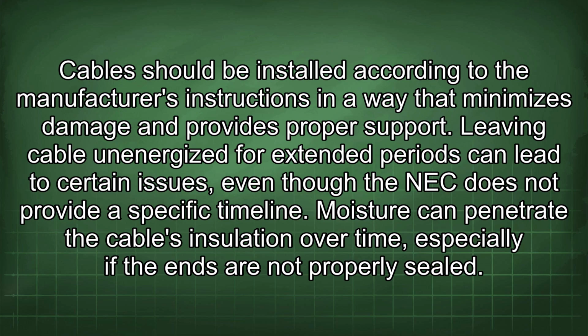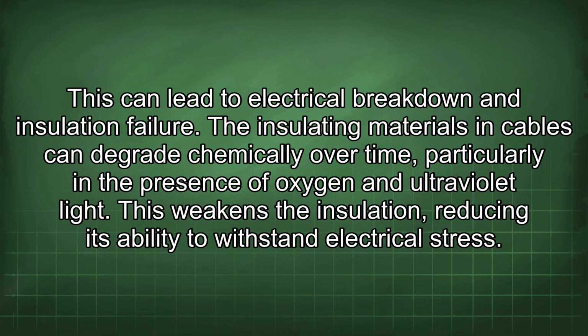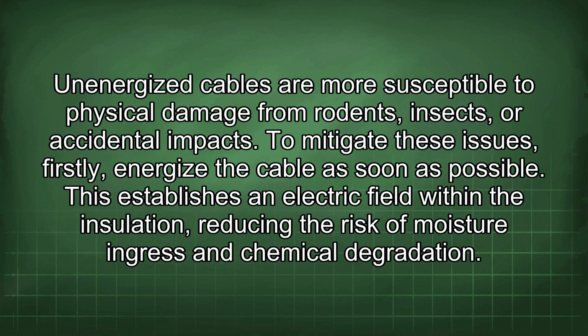Leaving cable unenergized for extended periods can lead to certain issues, even though the NEC does not provide a specific timeline. Moisture can penetrate the cable's insulation over time, especially if the ends are not properly sealed. This can lead to electrical breakdown and insulation failure. The insulating materials in cables can degrade chemically over time, particularly in the presence of oxygen and ultraviolet light. This weakens the insulation, reducing its ability to withstand electrical stress. Unenergized cables are more susceptible to physical damage from rodents, insects, or accidental impacts.